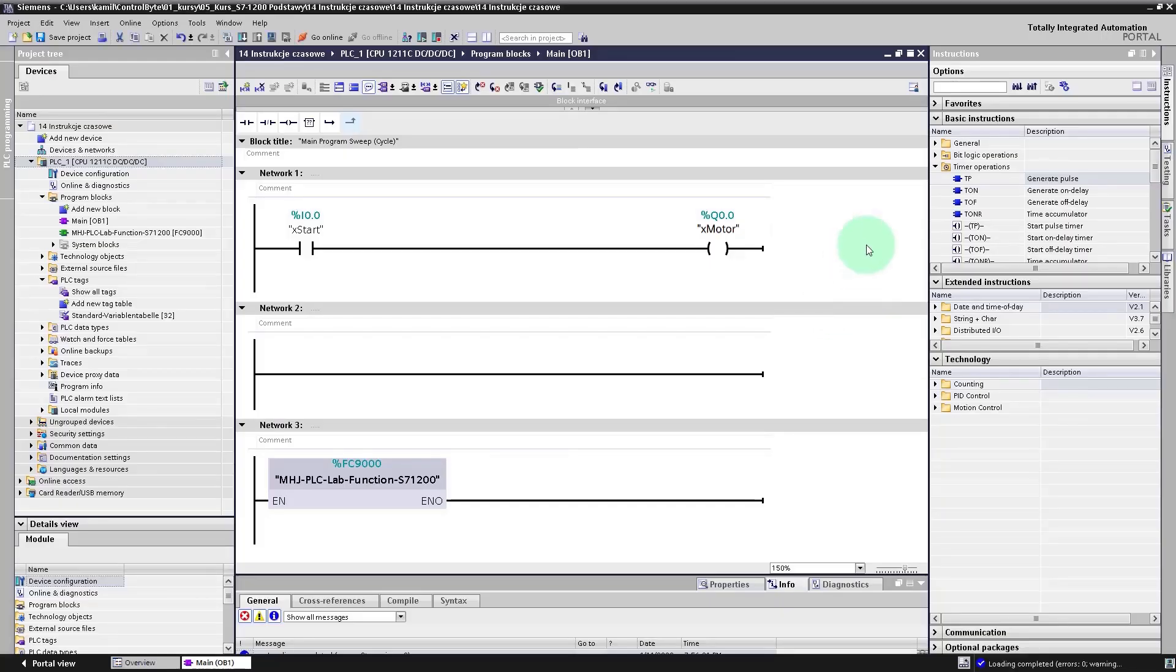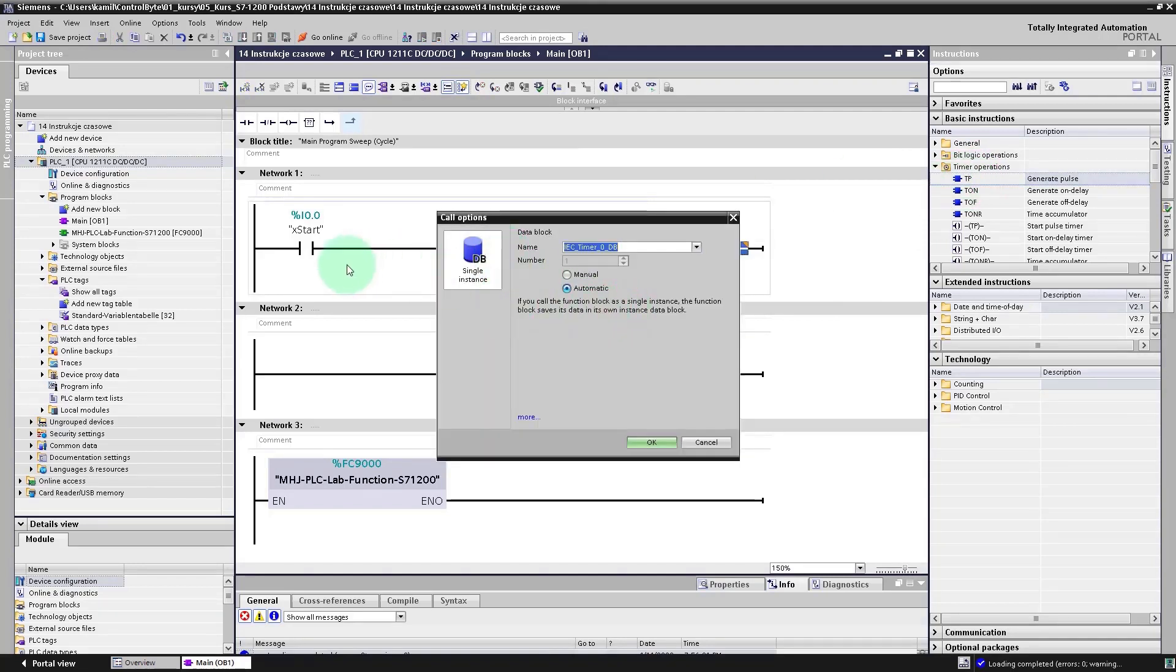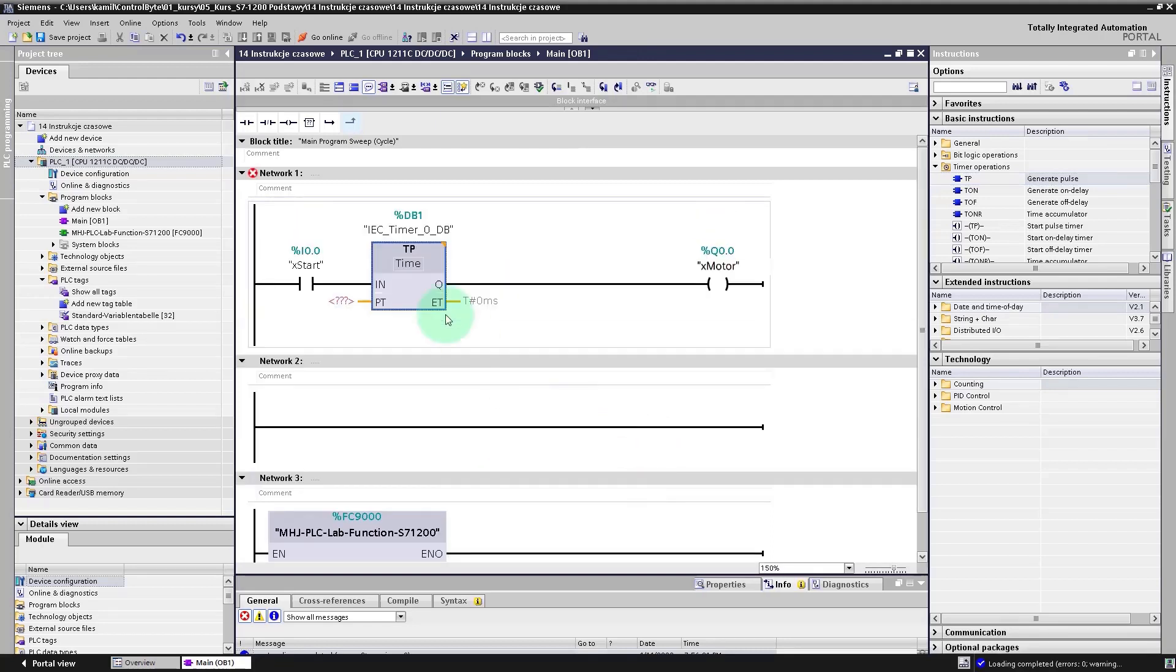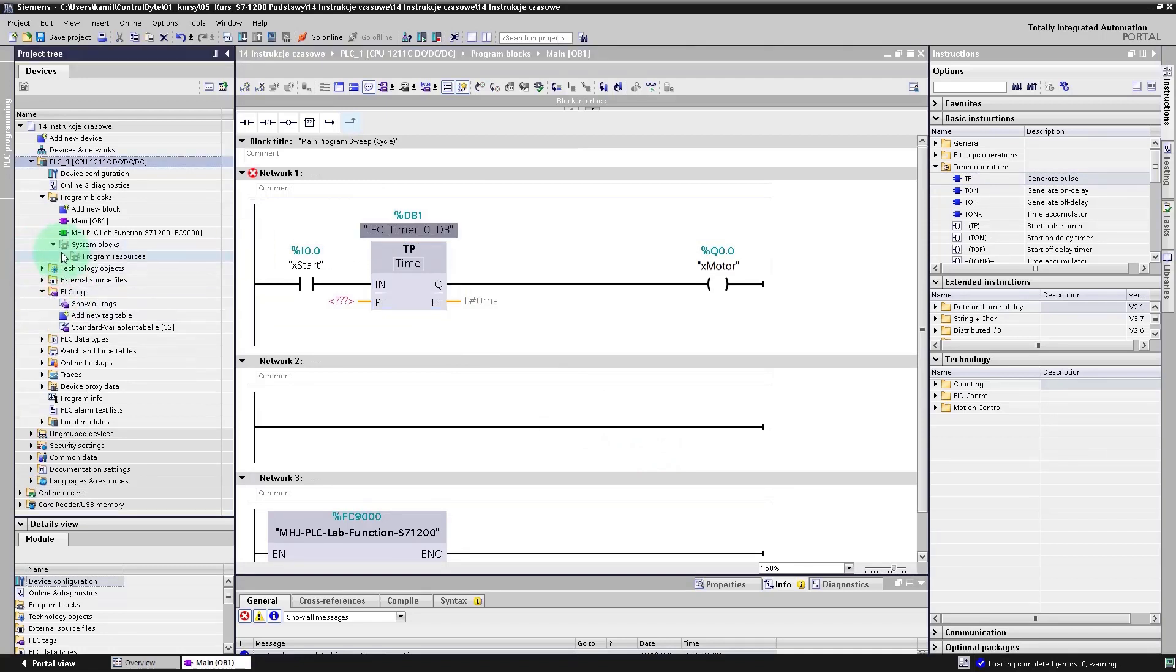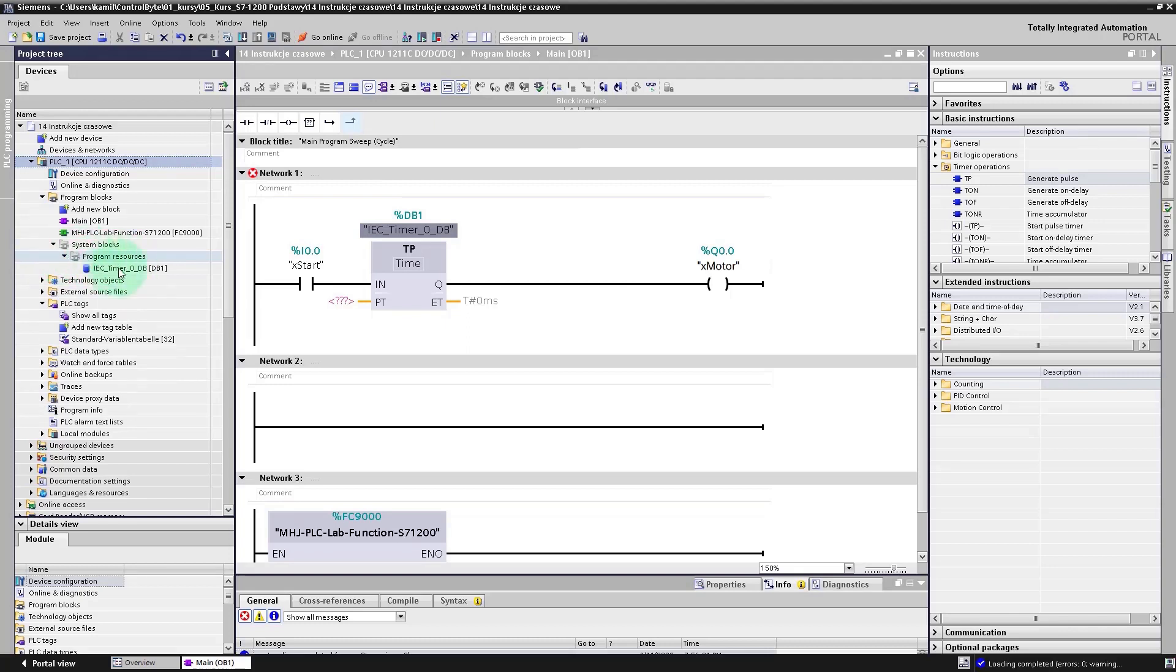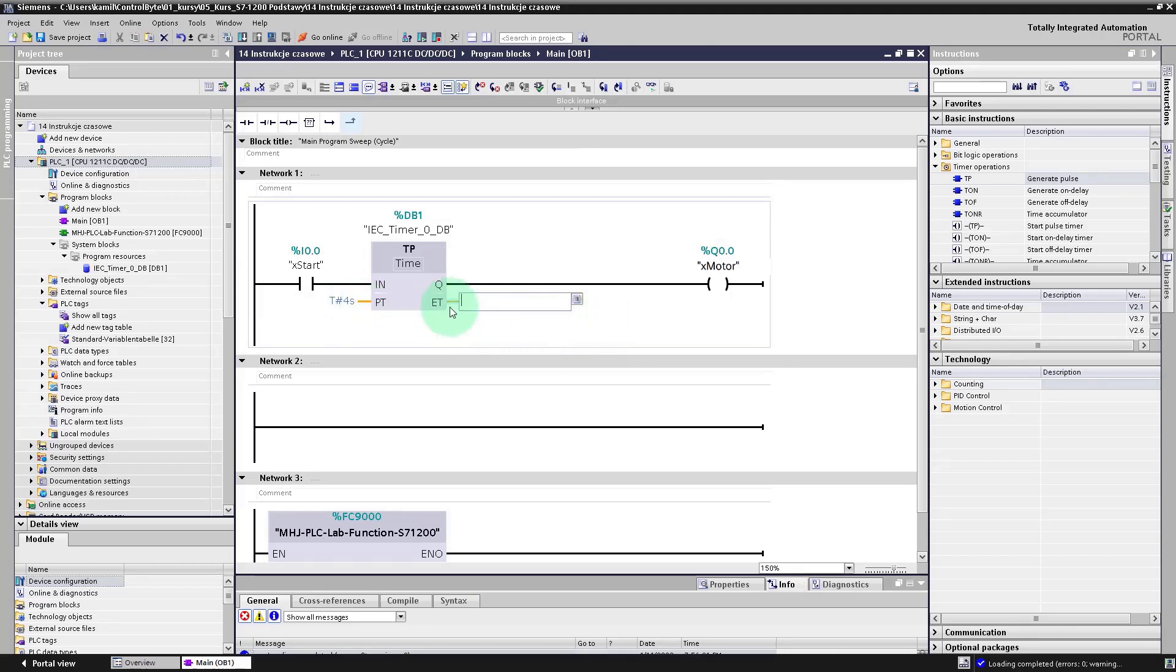OK, I will drag and drop TP timer from basic instructions here in first network. As you can see, we need to connect a data block to this timer. Click OK here. All declared data blocks you can find in project tree. Go to system blocks folder, next program resources. And here you will find all data blocks for timers, counters, etc. Next, add preset time. Just type here T hashtag 4S. It means that the pulse on the output of our block will last 4 seconds.